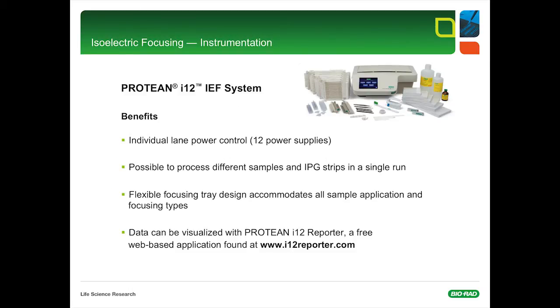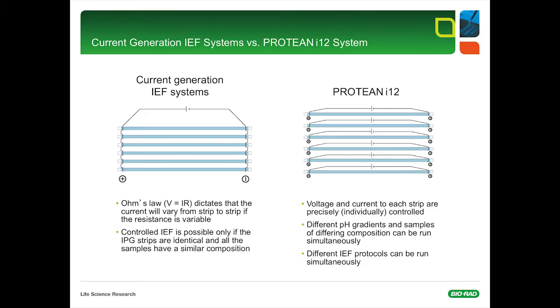This slide is about instrumentation for isoelectric focusing. Bio-Rad's Protean i12 IEF system is really the best instrument on the market because it offers individual lane control. The instrument provides 12 power supplies for 12 strips. Therefore, it's possible to process different samples and different IPG strips in a single run. This is not possible with other instruments. The focusing tray is very flexible and accommodates all sample application focusing types: gel side up, gel side down, and cup loading. Very important is data visualization, which is possible with the Protean i12 Reporter, a free web-based application found at www.i12reporter.com.